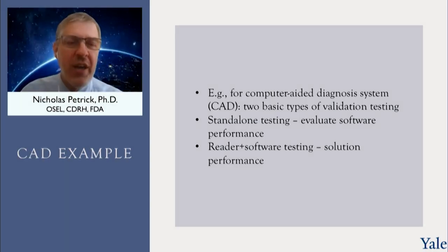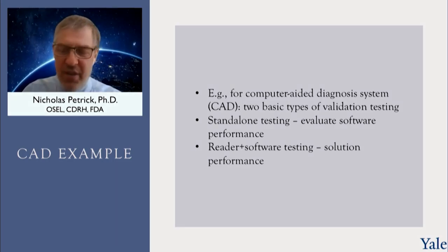We're again talking about a computer-aided, say, detection, so assist device, so the clinician's still involved in the diagnostics. We would follow a similar pathway. We would do that standalone testing because what we want to do with that testing is to benchmark the performance and make sure it meets its performance criteria.